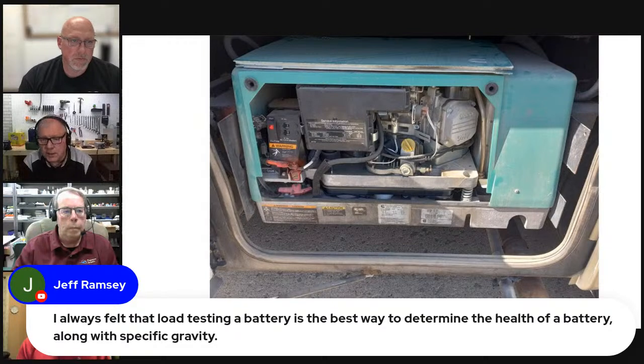What we've found with a lot of diesel generators is that if you don't run it under load, it's going to start to carbon up. It'll start and run fine, but it'll blow black smoke for an hour and a half, it seems like. So those are important things to do.